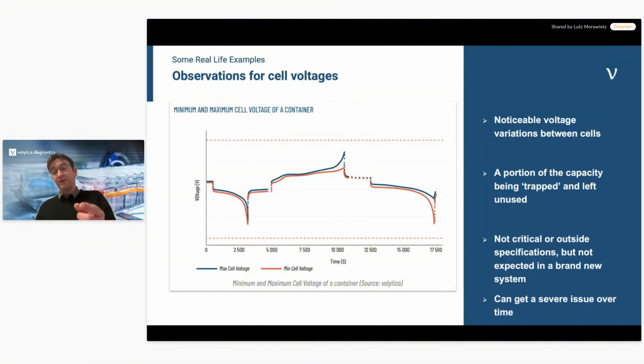As we don't know the reason for this disbalance, it can become a severe issue over time. If the disbalance increases, one cell might be stressed more than the other, leading to that cell dying earlier and even causing severe failures. Or the voltage spread increases and voltage limits are breached. So this was another case where we went back to the manufacturer and asked him to confirm or explain the reason why this battery is so disbalanced.